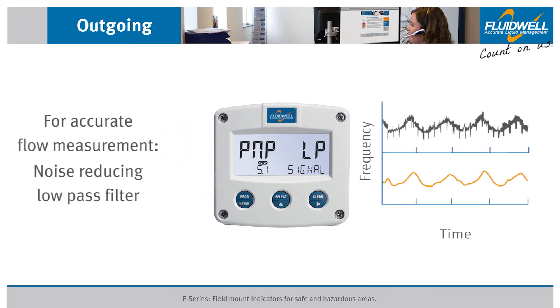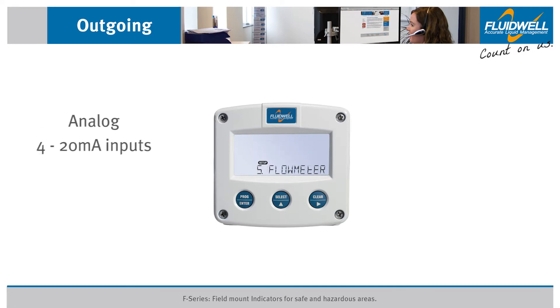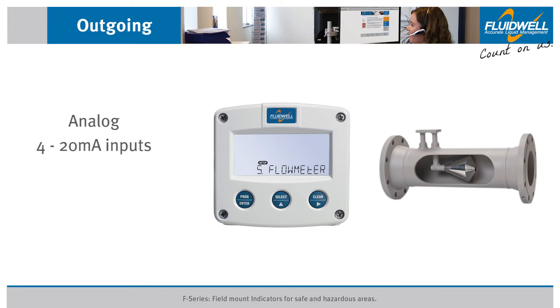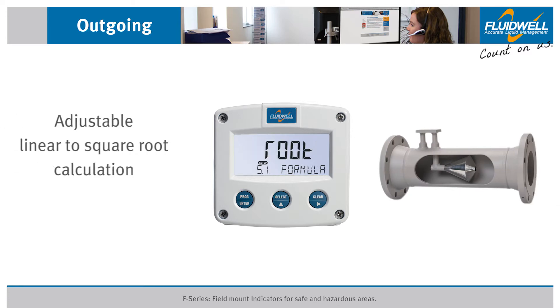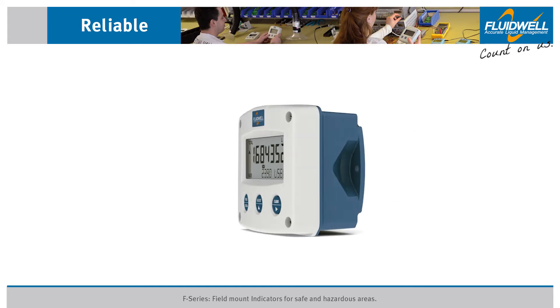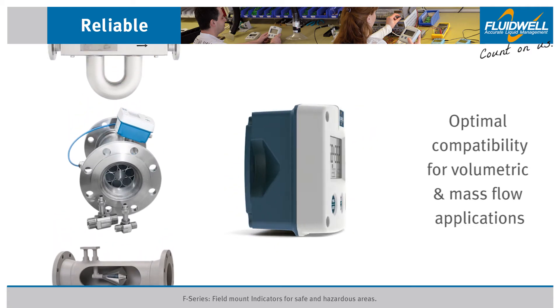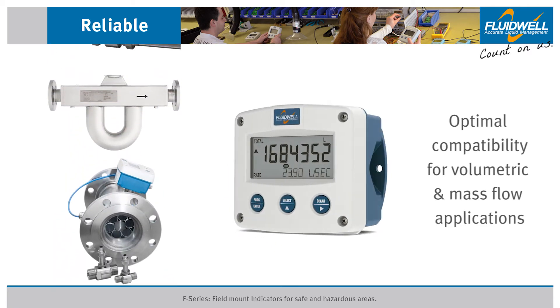A noise-reducing low-pass filter or linearization of the flow curve are available for more accurate flow measurement. For applications with analog 4 to 20 milliamps inputs, like differential pressure flow transmitters, the analog input is adjustable from linear to square root calculation. This results in optimal compatibility with almost any flow meter for volumetric and mass flow applications.